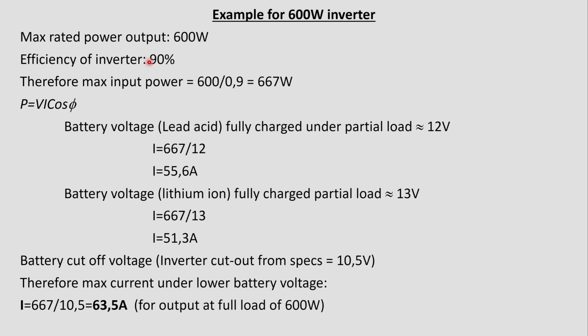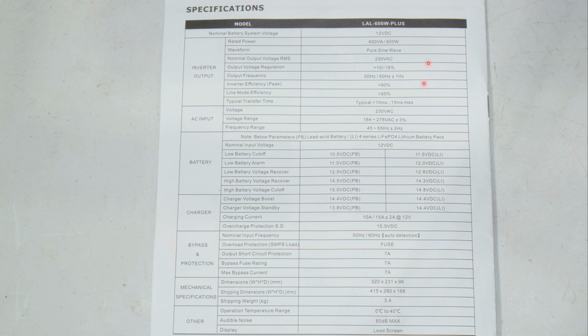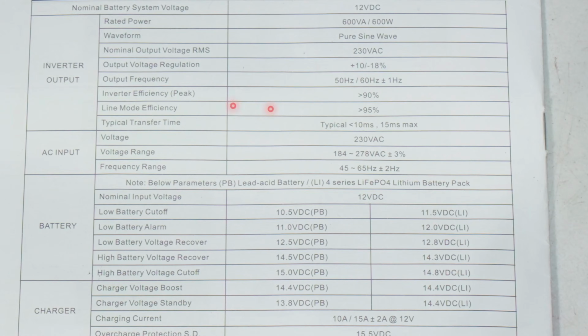If the inverter is only going to provide me with a 90% efficiency, that means that I take 600 watts divided by 0.9 and I get 667 watts. So that means that the battery needs to provide 667 watts in order to provide me 600 watts on the output. For example, here are the specifications of the inverter. There it says the rated power is 600 watts. It also shows over here the efficiency, but when it's on battery or inverter mode, it is better than 90%. So I've just taken 90% as the efficiency.